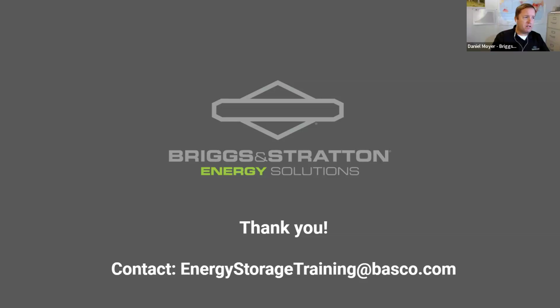Shannon's asking, I'm not sure exactly, does the gateway require power? The gateway consumes a little less than 5 watts of power, and it is powered by DC power. The power for the gateway is drawn from the 48-volt DC bus. It doesn't use much power at all. It's 4 to 5 watts. But yes, it does consume a little bit of DC power. It's probably a little higher if you use Wi-Fi versus using the network adapter instead.